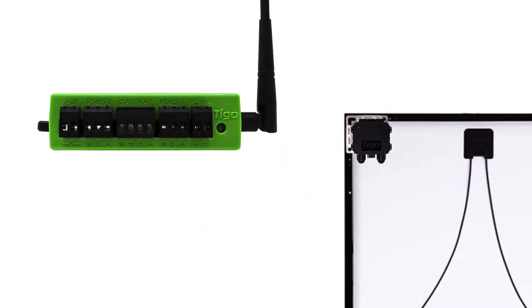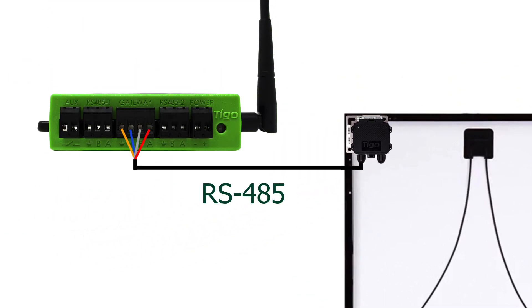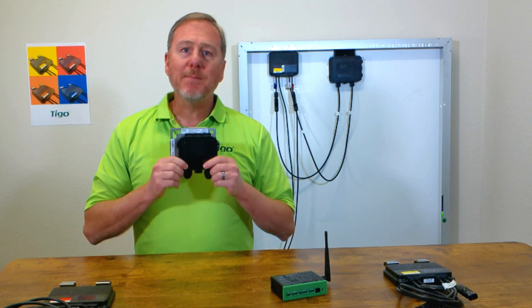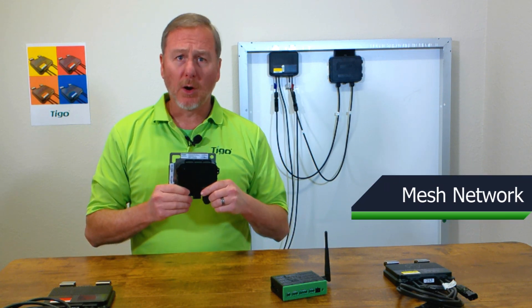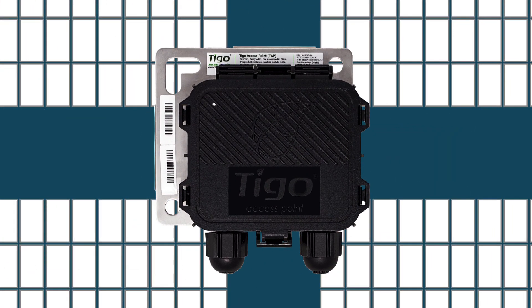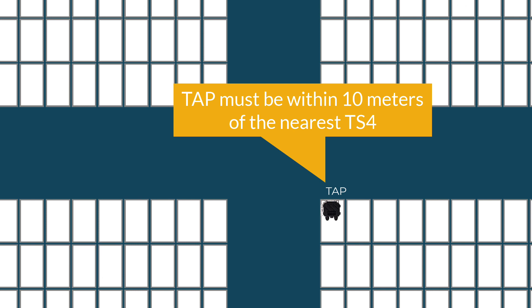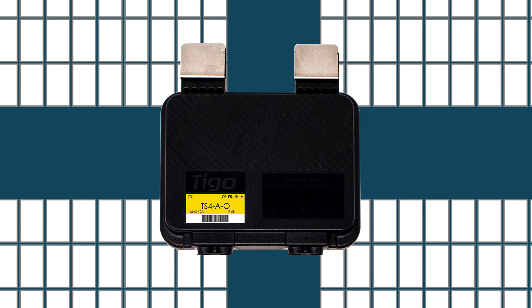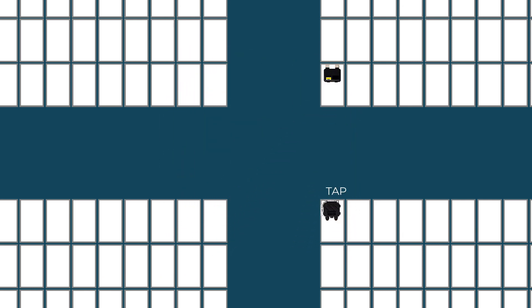The CCA will be mounted in a water-tight enclosure on ground level. They are connected together with an RS-485 cable. The TAP uses a mesh communication architecture, which means as long as a TAP is within 10 meters of a TS4, each TS4 in that mesh area will be able to communicate to this TAP.